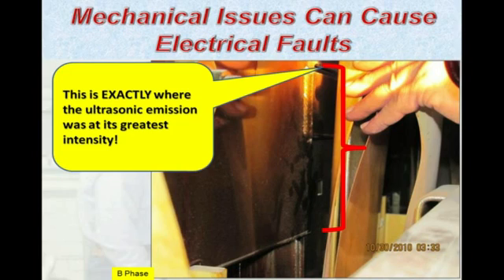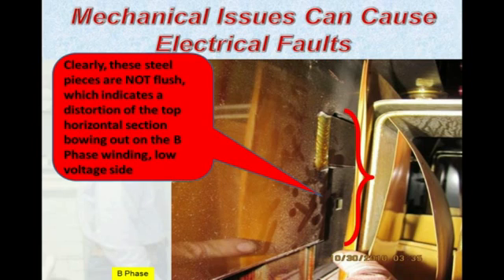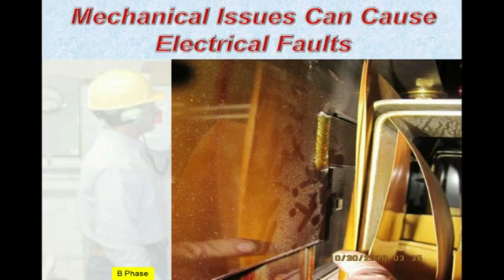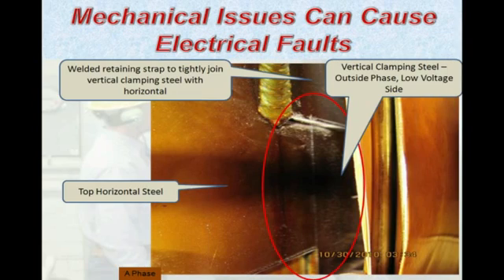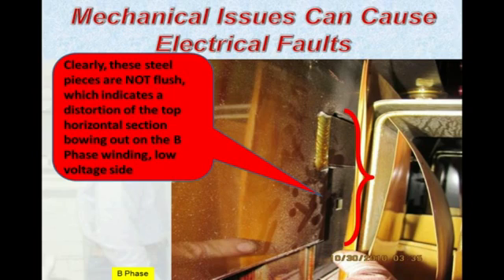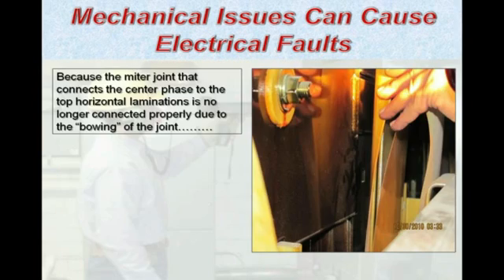So we had a comparison between this miter joint, which was on the B phase, and the A phase right here. This isn't necessarily showing the varnish on the laminates, but if I go back to this slide here, down on the bottom of the screen where the horizontal piece comes up from the winding, the thermal energy was transferring down into the winding and onto the core laminates. So the heat transfer caused a chain reaction effect on the bubbling or the beading of the varnish here on the core.